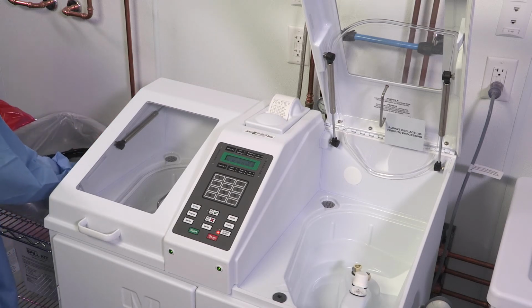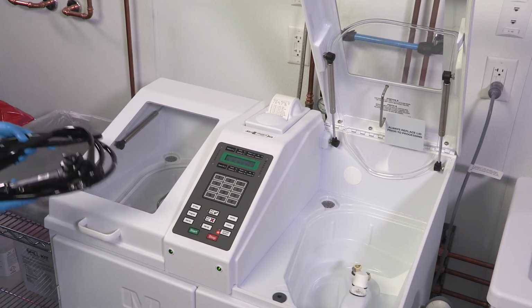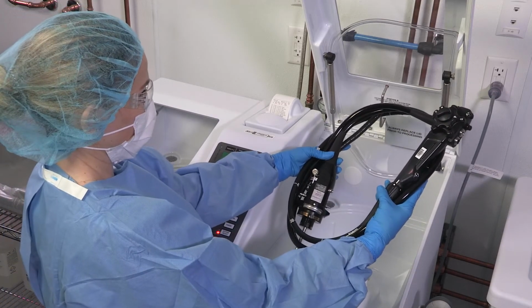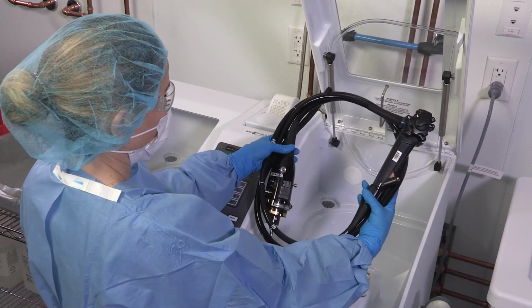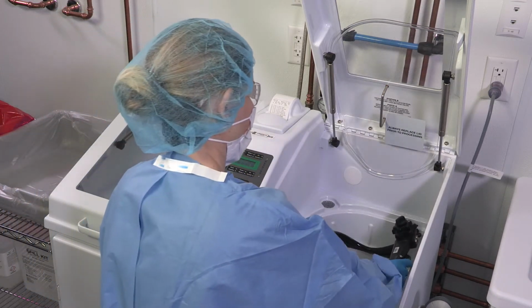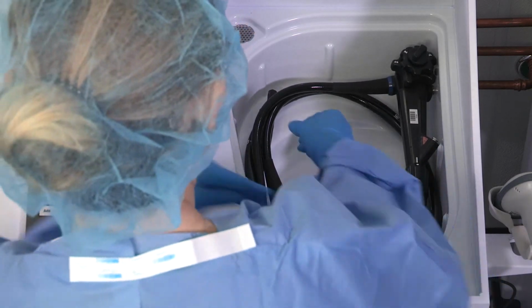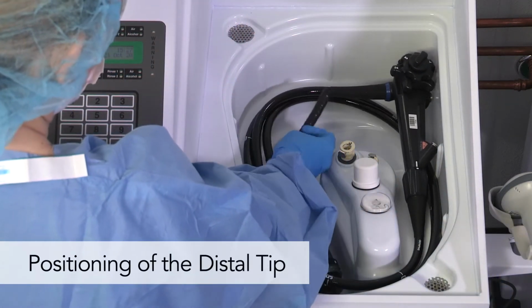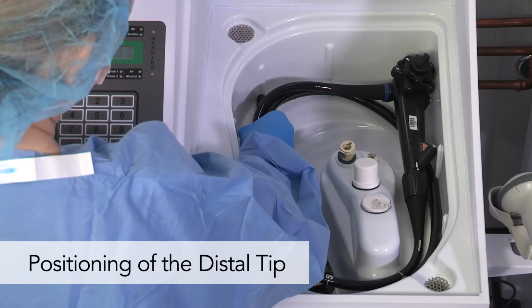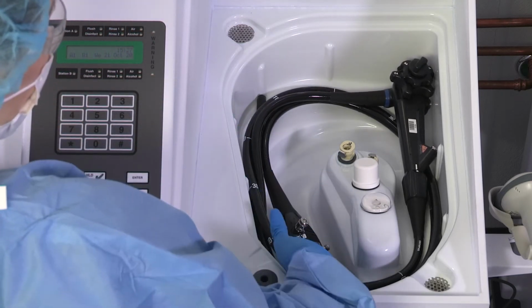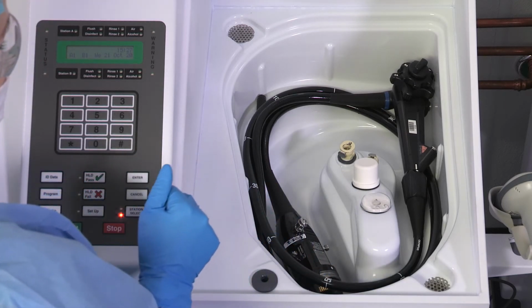To pre-coil the endoscope before placing it inside the basin, hold the control section in your right hand and loop the light guide cable in a counterclockwise fashion so that the light guide connector will land on the left lower side. Loop the insertion tube in a clockwise motion in an oval shape to fit in the basin. Place the control section at the right rear of the basin with the control knobs up. The distal end should be tucked under the endoscope to ensure fluids do not shoot up and onto the floating lid or down the overflow drain.